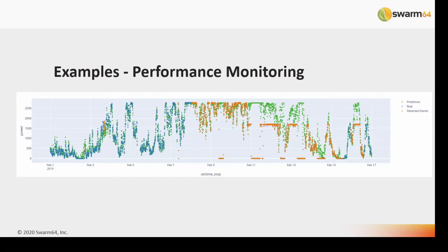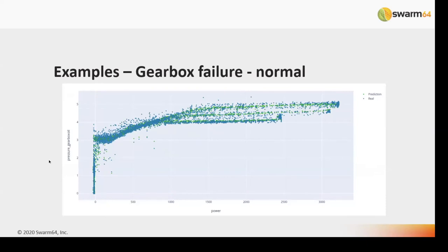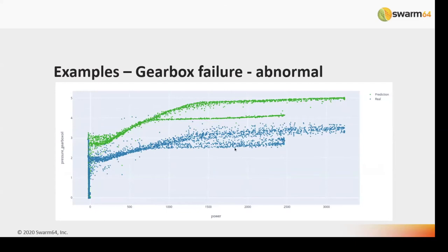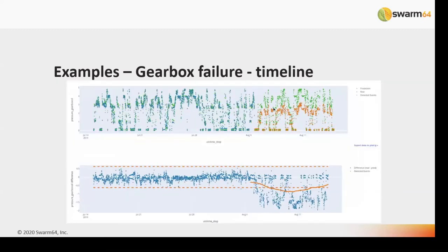Another example: on the y-axis is gearbox oil pressure, and on the x-axis is power. You can see the turbine's different operating states. This is normal behavior — but here the pressure has dropped, shown in blue as the real values and green as the predictions. Something was wrong: the oil cable connections had broken, causing a pressure drop. You want to proactively detect this — when the pressure starts to drop, you need to act before the turbine enters a problematic state.